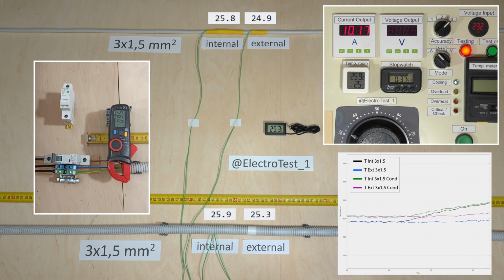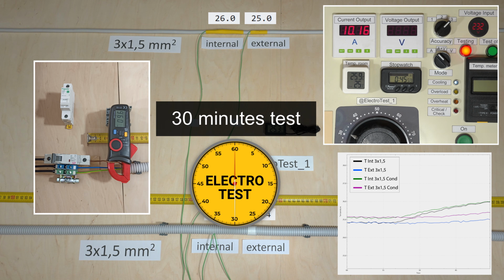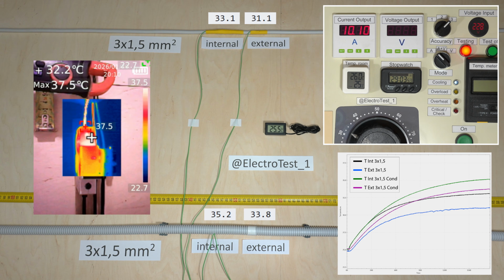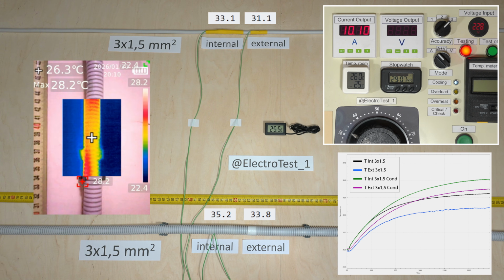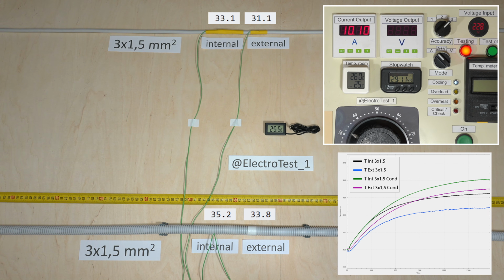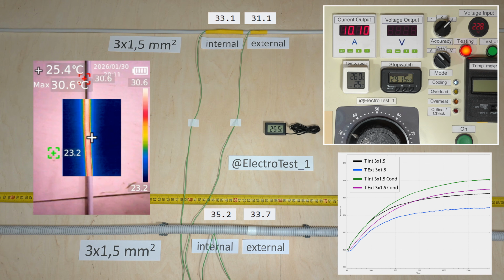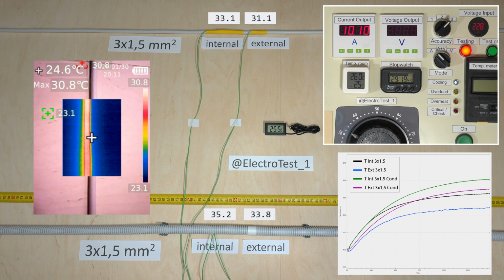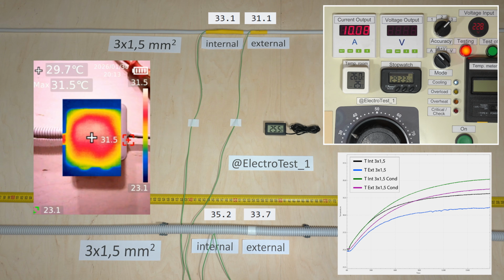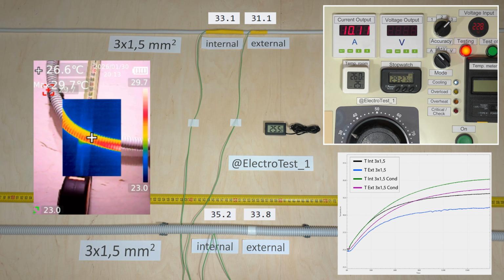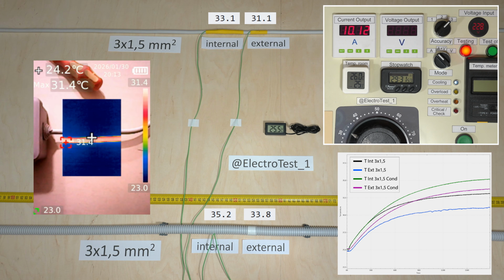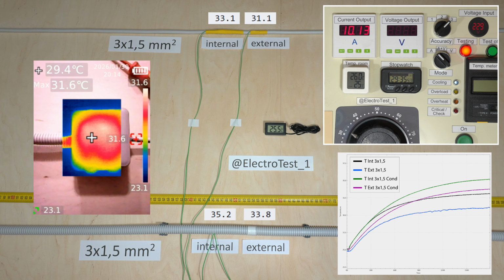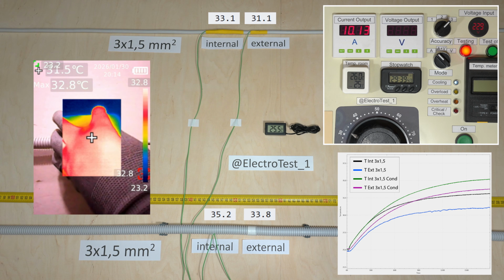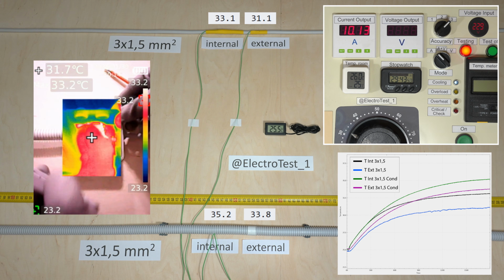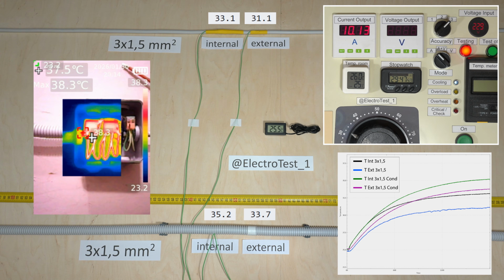At first, the internal temperatures rise equally. You can also see the heating of the circuit breaker and the conduit. The outside temperature of the box is about 30 degrees Celsius, while inside it is almost 40 degrees Celsius. The difference is noticeable.